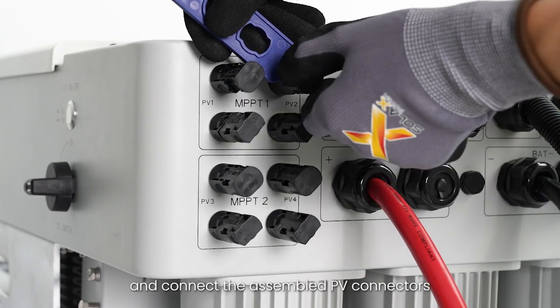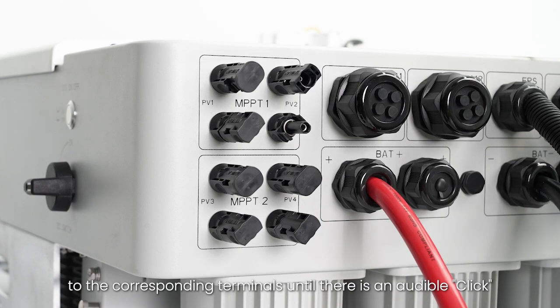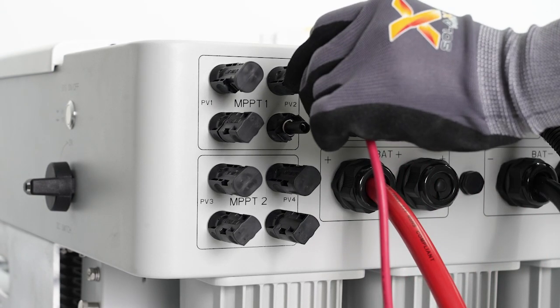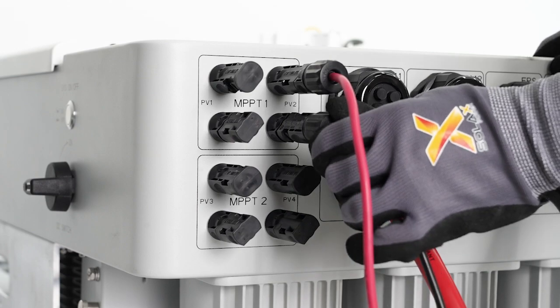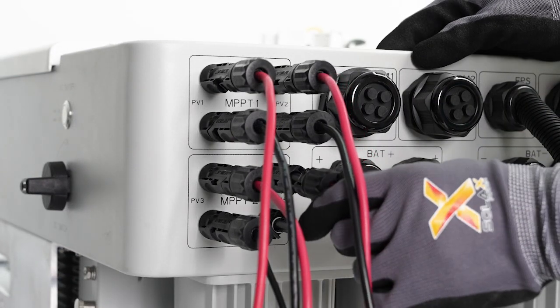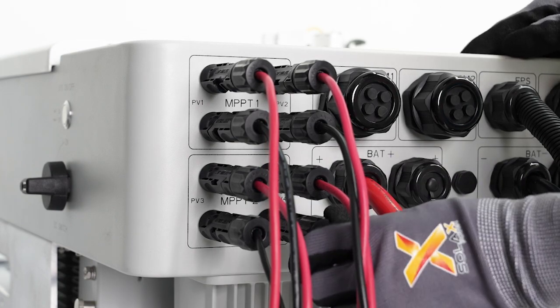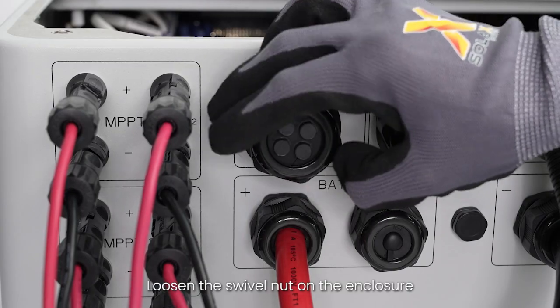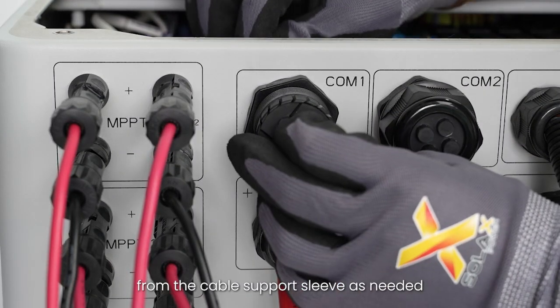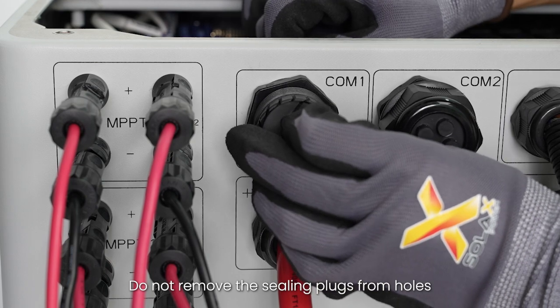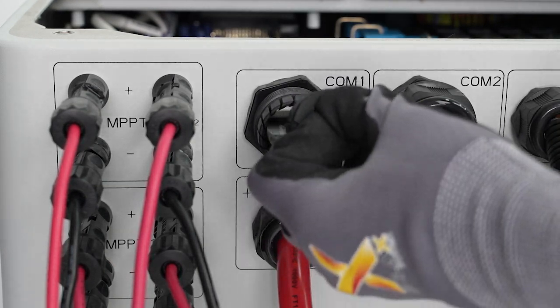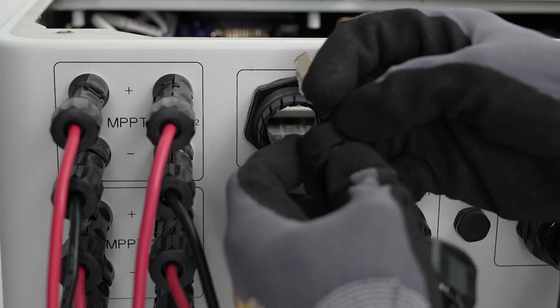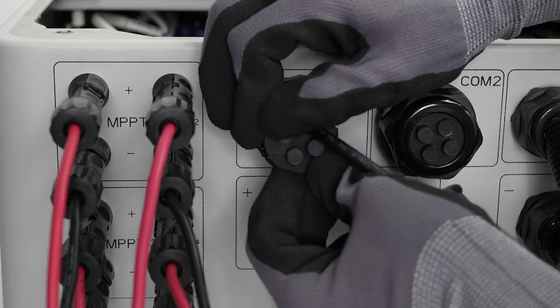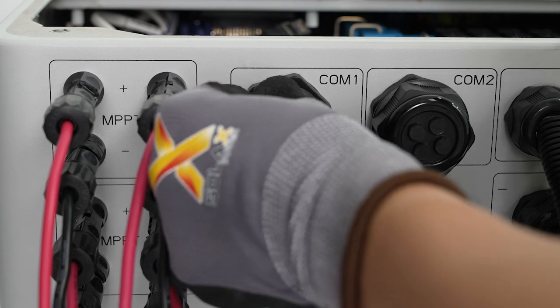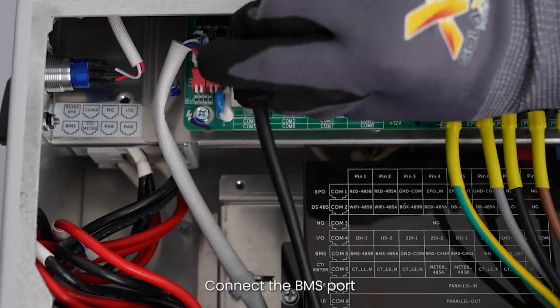Remove the PV terminal caps and connect the assembled PV connectors to the corresponding terminals until there is an audible click. Loosen the swivel nut on the enclosure, and then remove the sealing plugs from the cable support sleeve as needed. Do not remove the sealing plugs from holes if you choose not to connect the cable. Connect the BMS port.